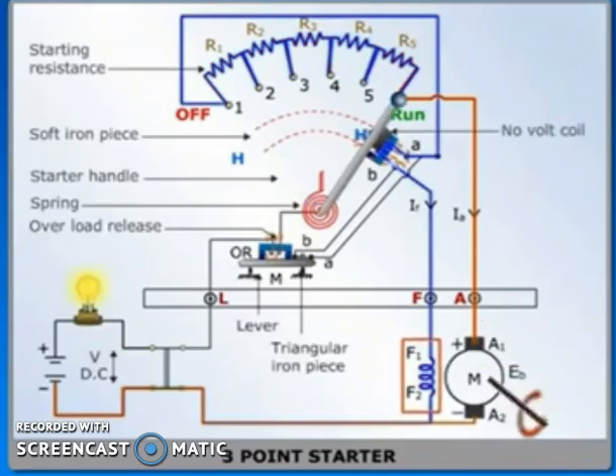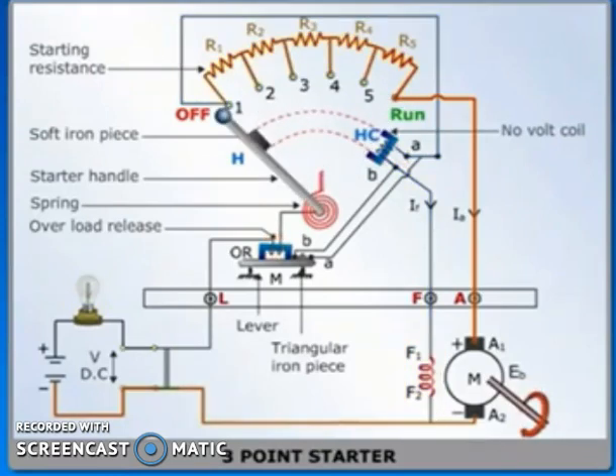Limitations of the three-point starter: If speeds above normal are to be obtained, the field current must be reduced. At a certain value of reduced field current, the electromagnetic pull of the holding coil may become less than the spring force. We know flux is inversely proportional to speed. As flux decreases, speed increases. At the point where flux is small enough, since IF is in series with HC magnet, its force becomes less than the spring force. In such a case, the starter handle returns to the OFF position and the motor stops.